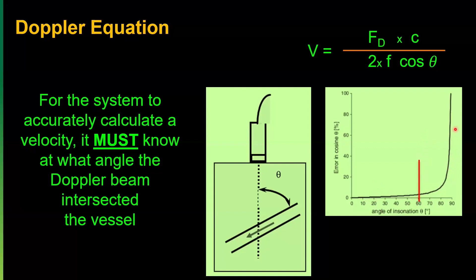So we have something at our disposal called angle correction. Every system has it. That angle correction cursor, which is this straight green line here, must be parallel to the vessel walls. So in this example, it's correct. I could believe the velocities that the system is telling me. In this example, it's not correct.